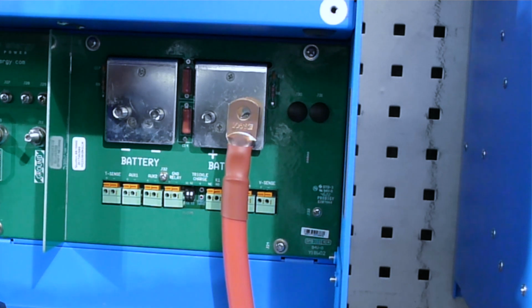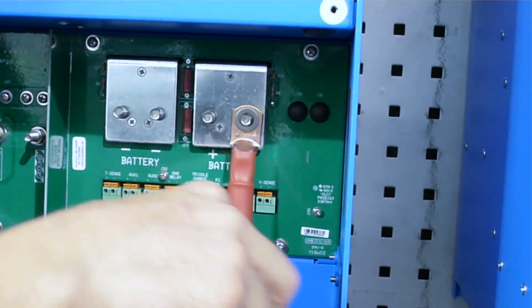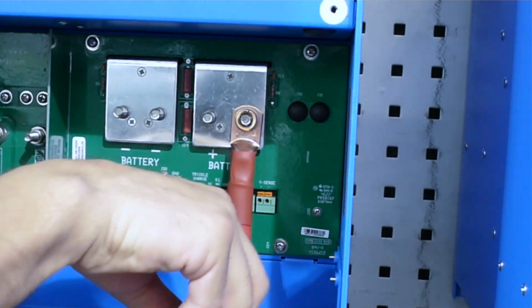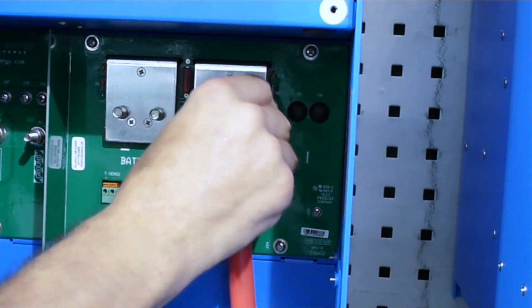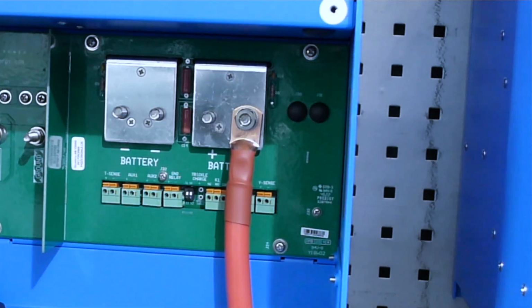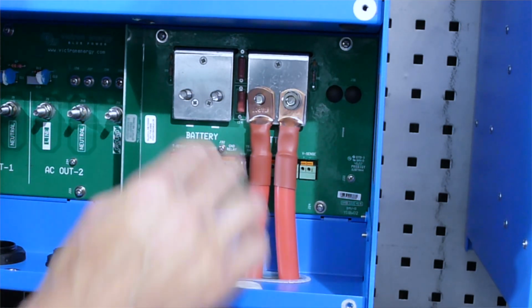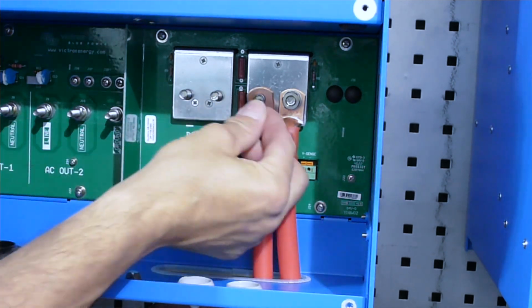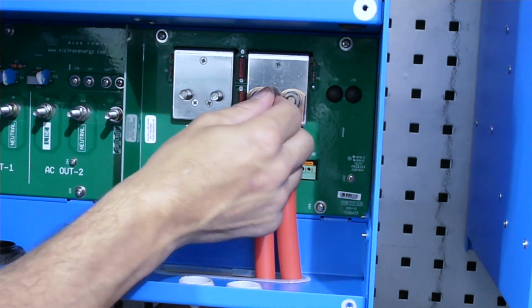Let's connect the battery cables, 2 red ones for positive and 2 black ones for negative terminals. Always use a flat washer followed by a spring washer and a nut. Secure it to max 40 Nm torque.